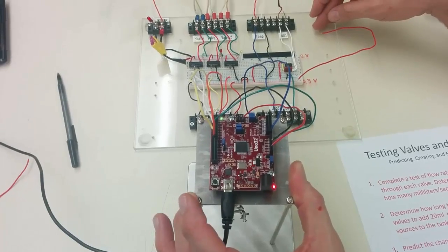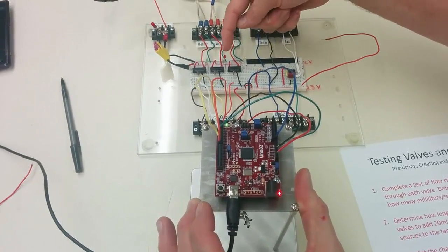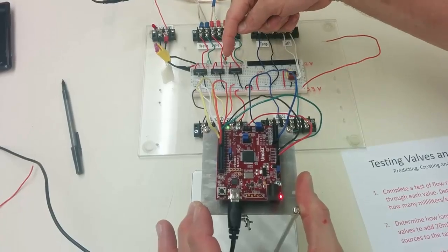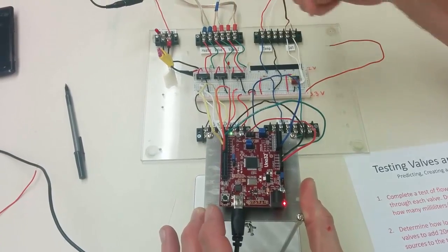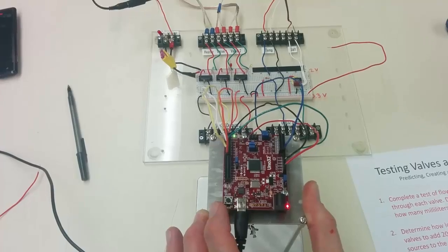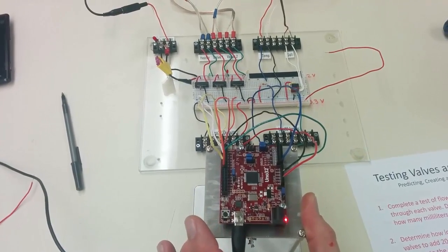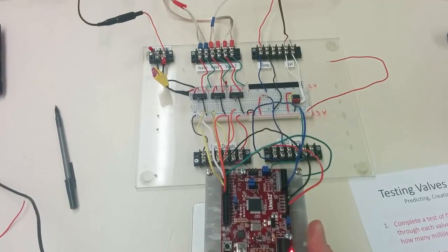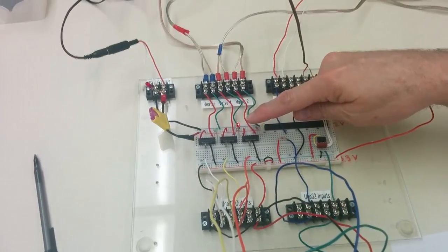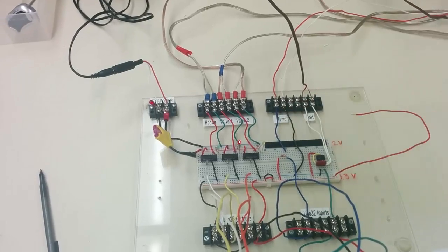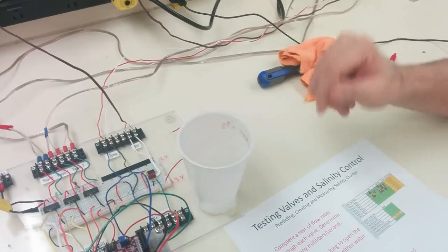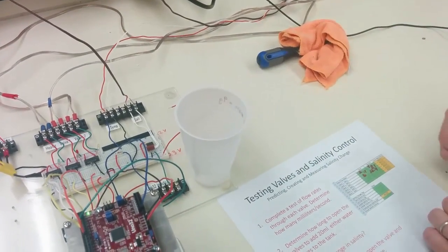Change the program to do our 4-second trial. I'm going to hit the reset button. You'll see the DI water valve operation start here, and you'll hear the click in the background. We'll capture the water there and measure that mass as well. Press this, wait for about 4 seconds. 1, 2, 3, 4. And we've captured the water, and we'll weigh that to take our other piece of data.